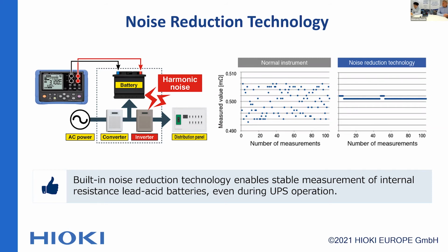We have not disclosed the details of this technology in order to keep competitors from knowing about it. To tell the truth, BT3554 has three test frequencies around 1 kHz, plus or minus 50 Hz. If you enable the noise reduction function, it automatically selects the proper test frequency. It may take a longer test time while the function is enabled, but you can get a stable test result. Of course, measurement accuracy is guaranteed at all test frequency points, so you don't need to worry about accuracy changes.